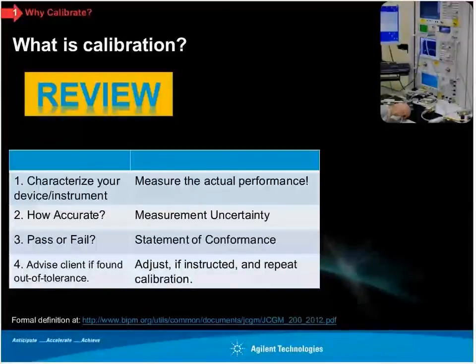And 17025 tells us that you're supposed to advise the client if your device or instrument is found out of tolerance. So at Agilent, what we do is, unless someone instructs us otherwise, whenever we find an instrument out of tolerance, we go ahead and adjust it. We repeat the calibration procedure and then provide the customer with both sets of measured data so that they know how it performed when it came in and how it is performing as we've sent it back to them.